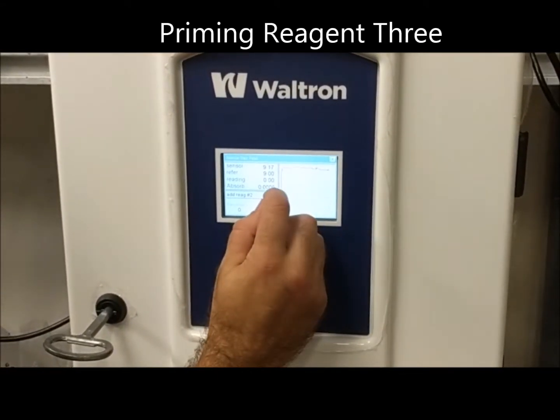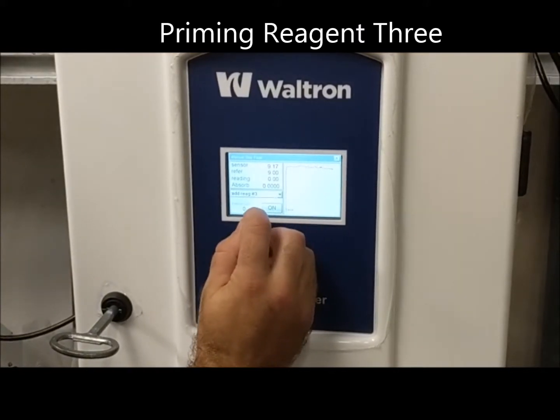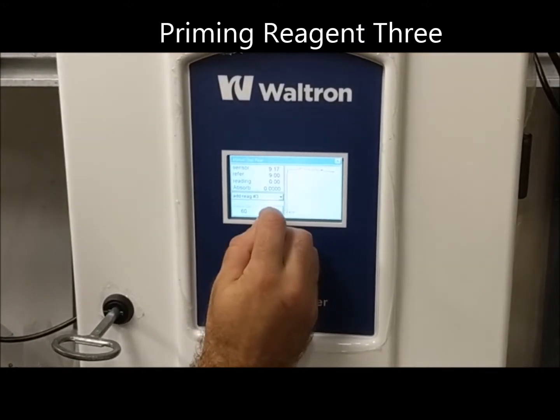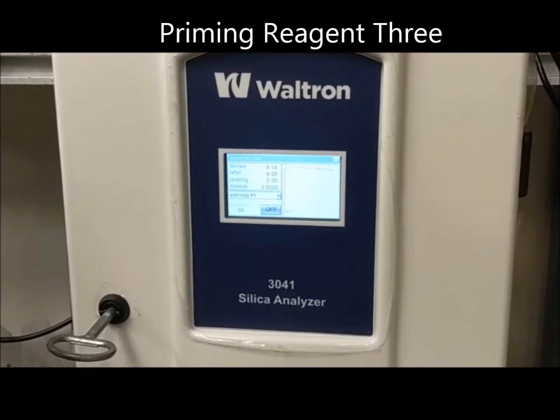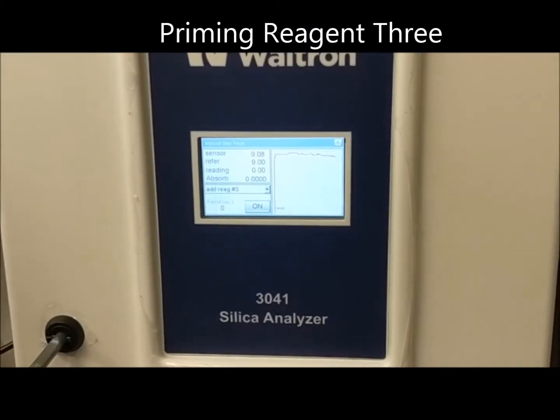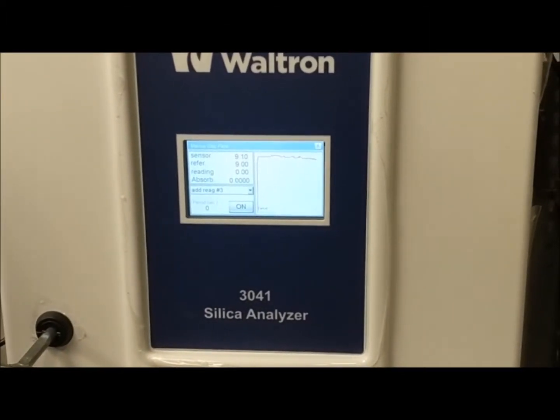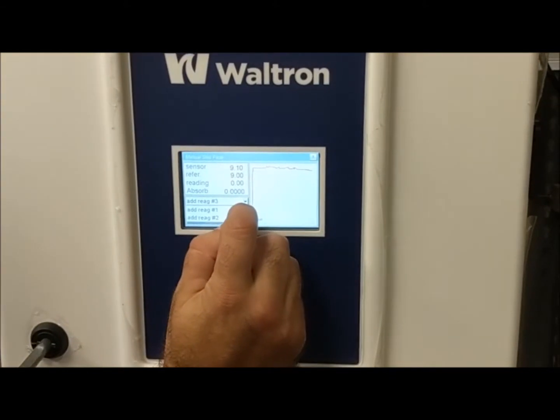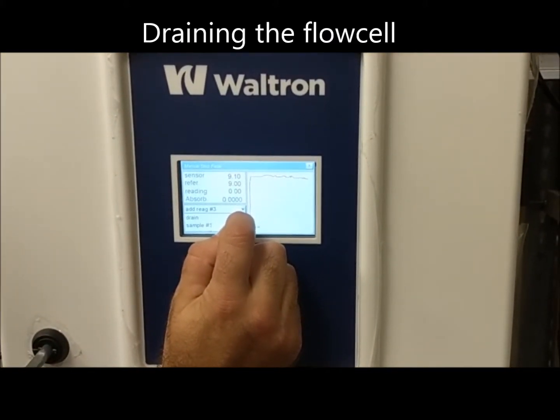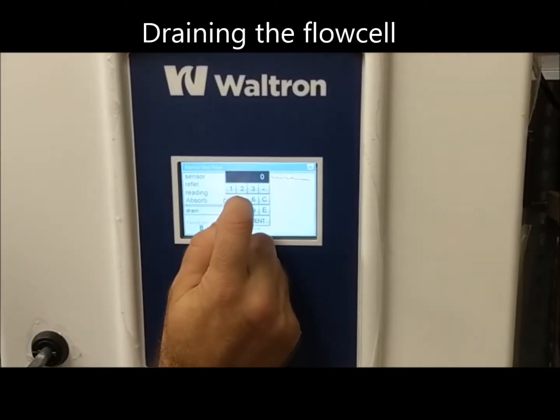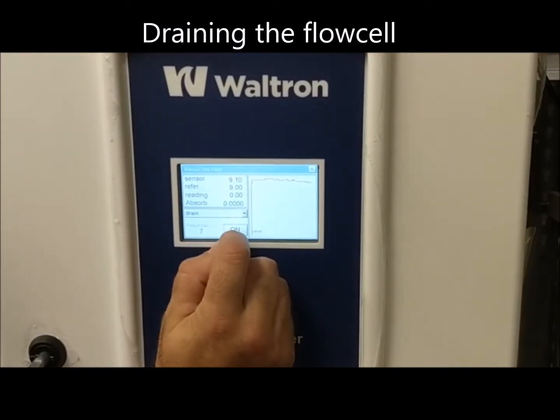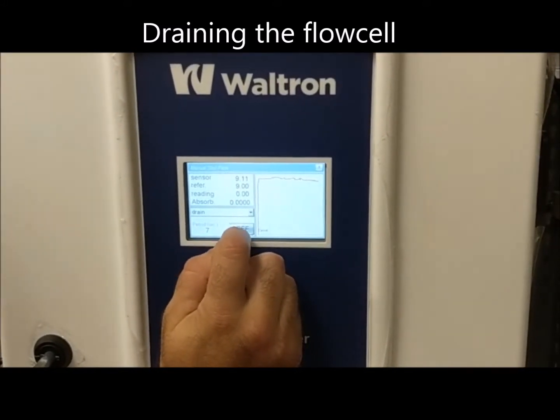Once reagent 2 is complete, scroll down to reagent 3, also 60 seconds. Once all 3 reagent lines have been primed, it's a good idea to come back to our selection, do a drain command for 7 seconds. Now make sure the flow cell is empty of all the reagents that we just primed the lines with.